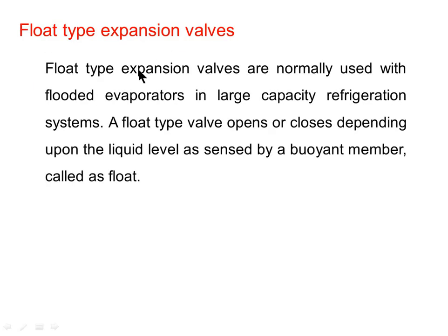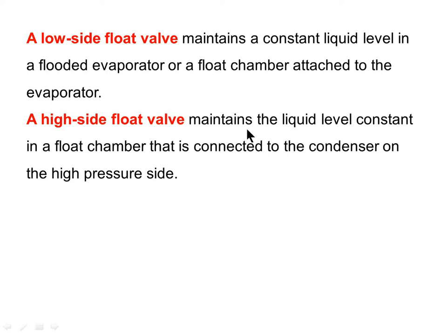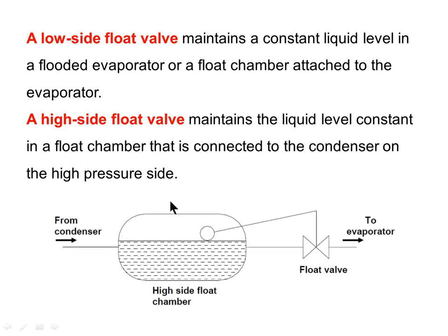Float type expansion valves are normally used with flooded evaporators in large capacity refrigeration systems. A float type valve opens or closes depending upon the liquid level as sensed by a buoyant member called a float. These are classified as low side float valves and high side float valves. A low side float valve maintains a constant liquid level in a flooded evaporator or a float chamber attached to the evaporator. A high side float valve maintains the liquid level constant in a float chamber connected to the condenser on the high pressure side, as shown in the diagram.